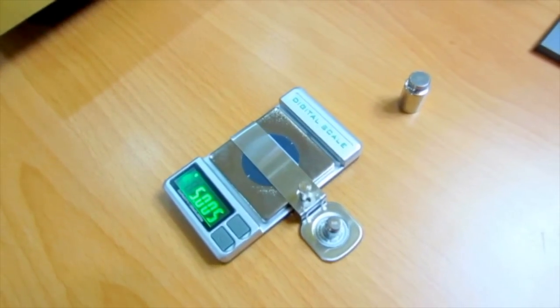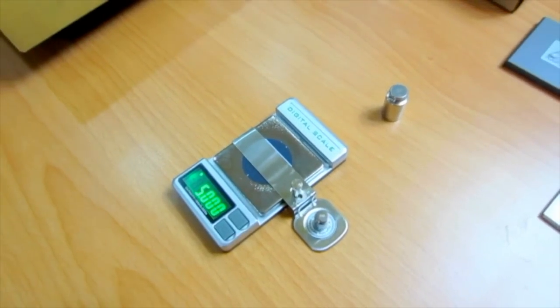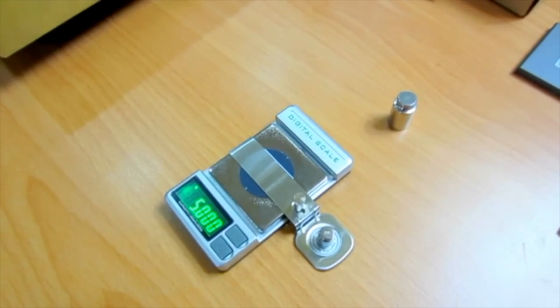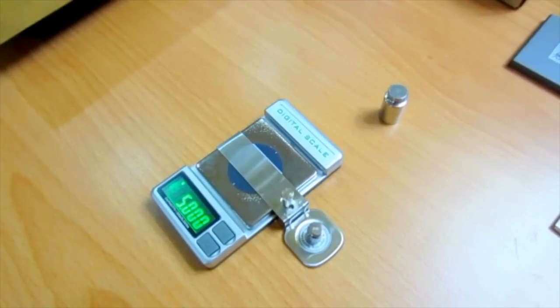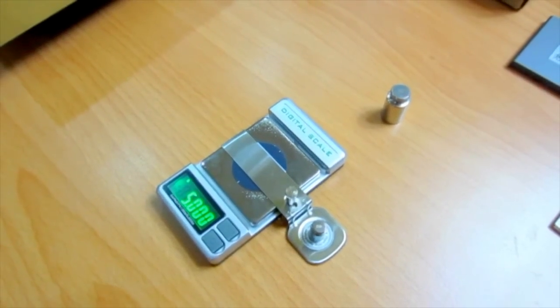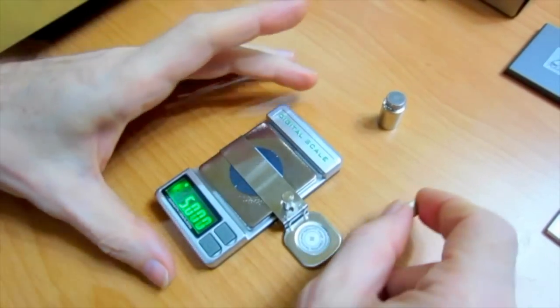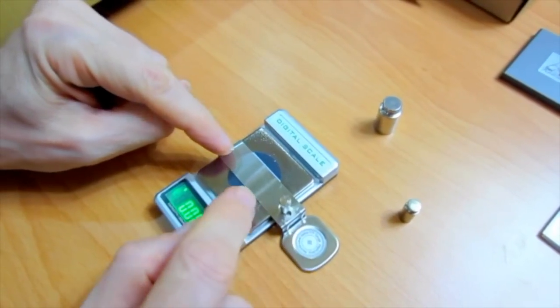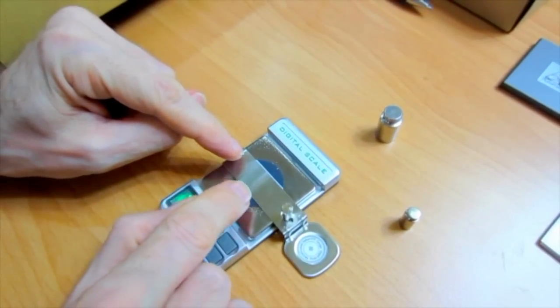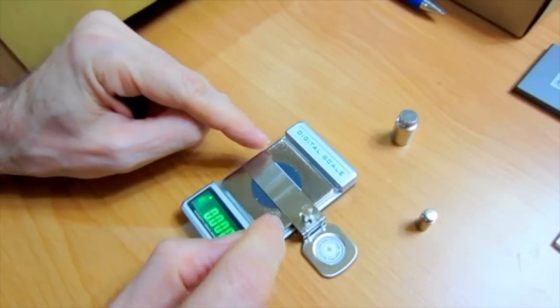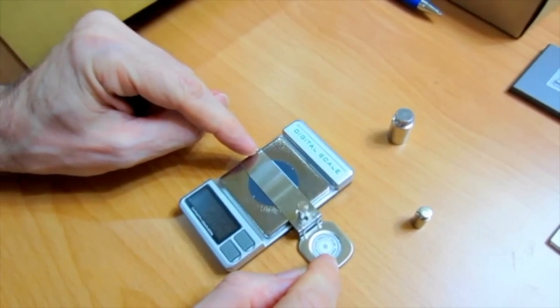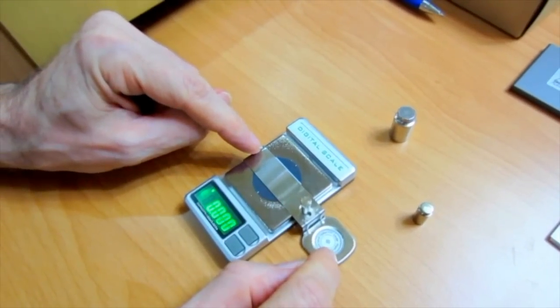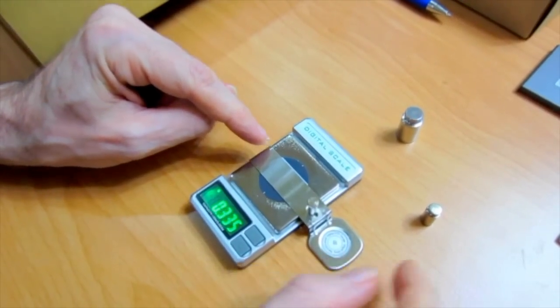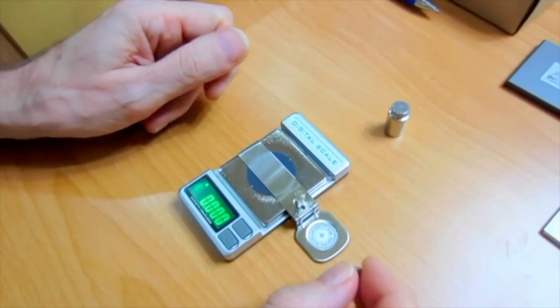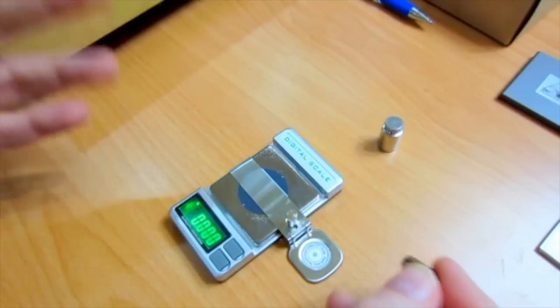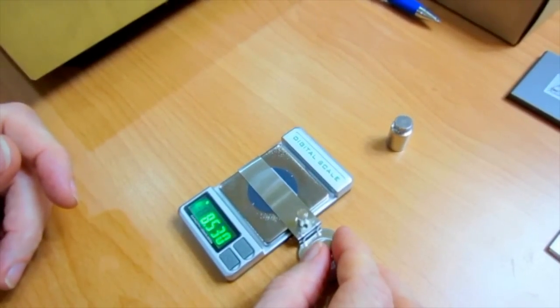That's the 5 gram mass. Let me stand back so I'm not breathing on it. We're actually okay as it is with the 5 gram mass, but again, it may or may not be, depending on ambient temperature. Also, there could be a slight influence because when you attach this arm, although we've got a very stiff beam, we designed it for a stiff beam, stiff plate, but there is a moment on the beam, and so that's why we always recommend recalibrating once the extension arm is on. But in this case, it's not any significant effect.